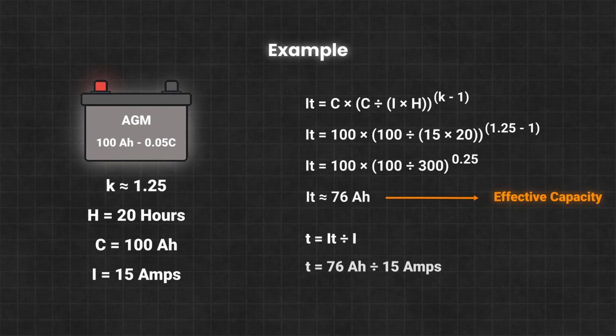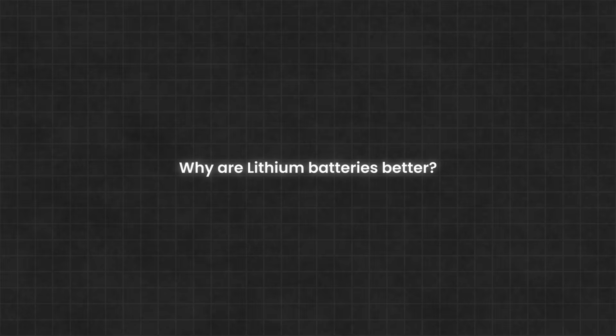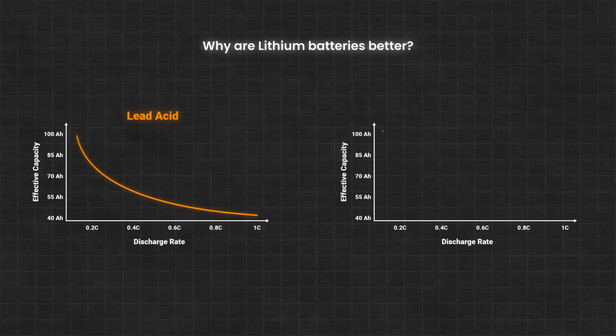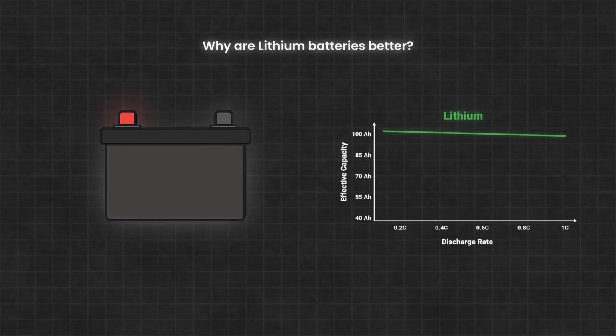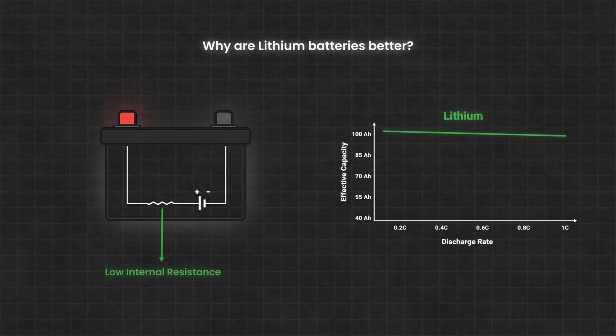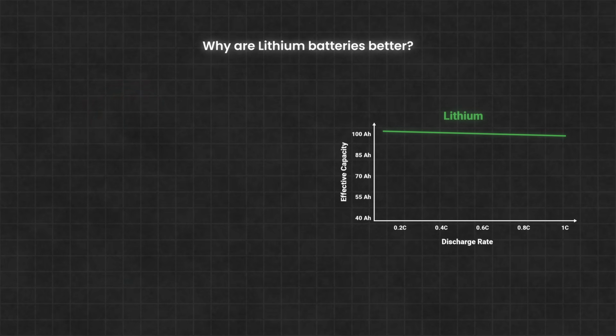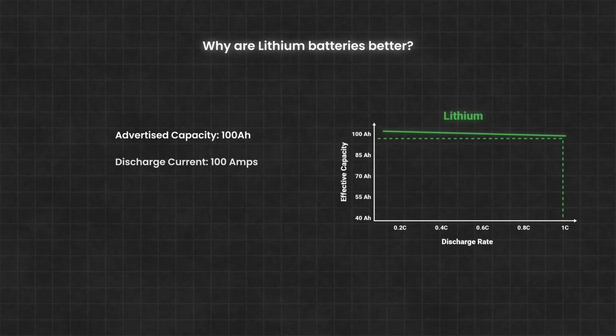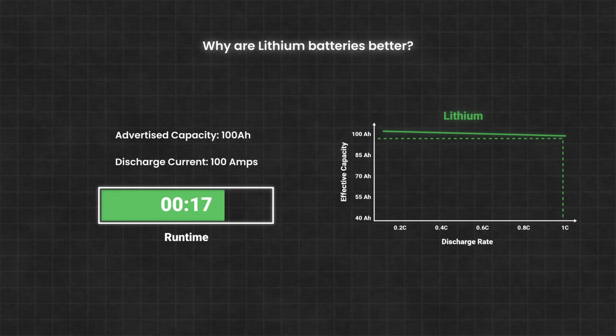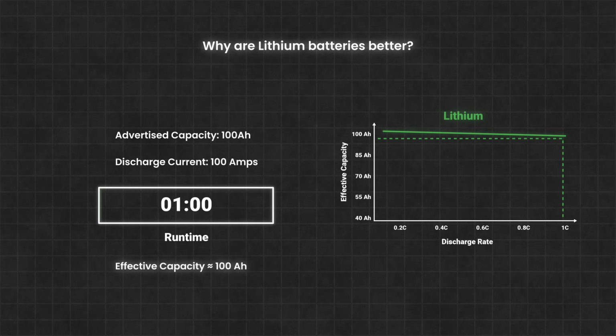Now to find out how long the battery will last, just divide the effective capacity by the discharge current. For lithium batteries, the situation is a bit different. These batteries are much better at maintaining their capacity even at high discharge rates, and that's due to their chemistry, which results in a much lower internal resistance. This means that if you discharge a 100 amp hour lithium battery at 100 amps, it will still last about 1 full hour, delivering its full rated capacity except maybe for a couple of amp hours.